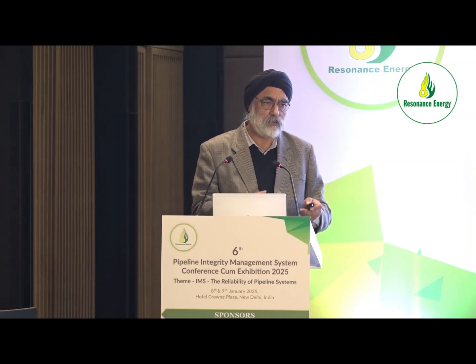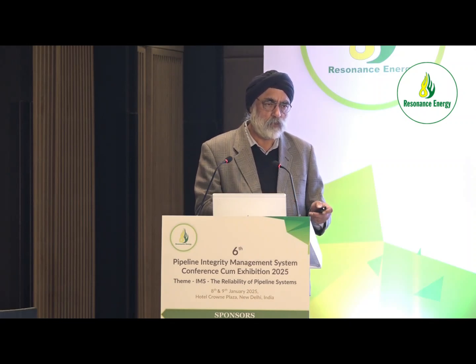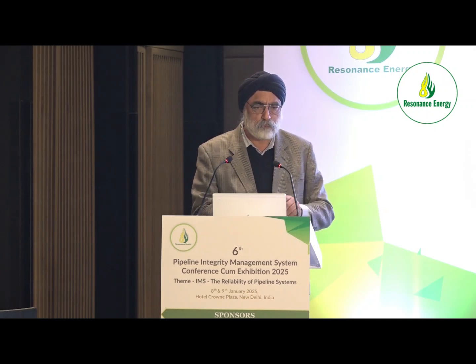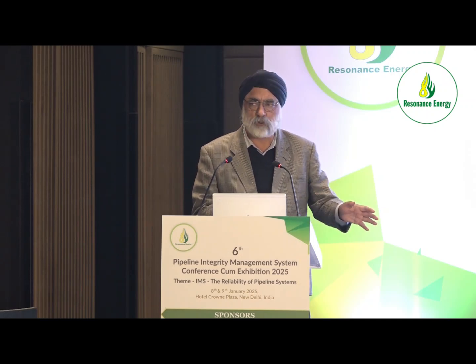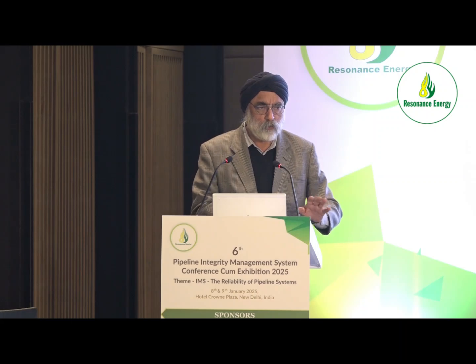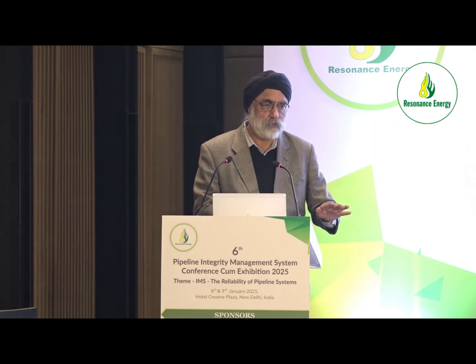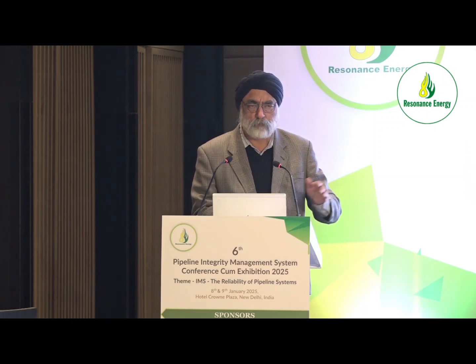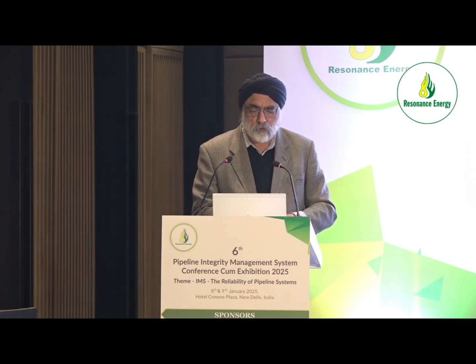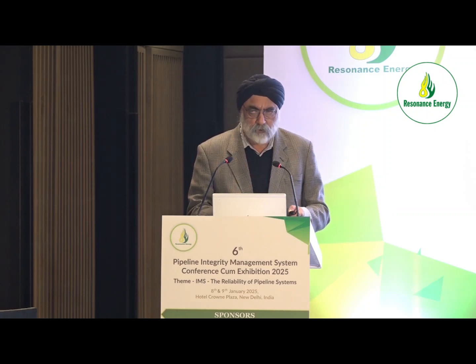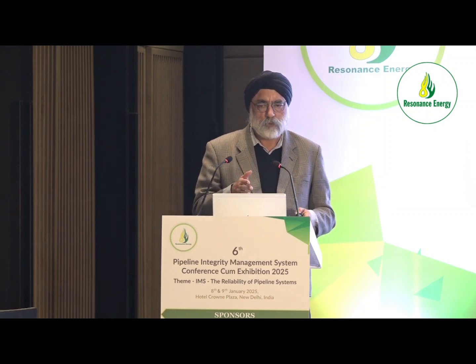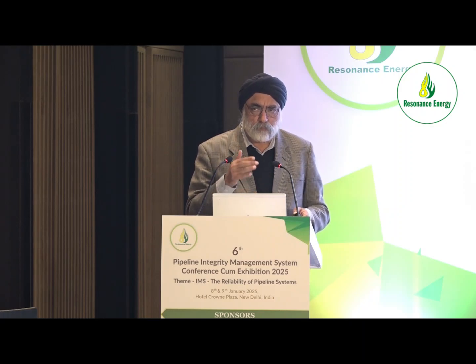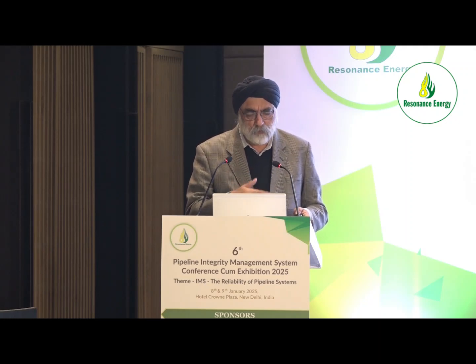We have to earth pipelines at regular intervals. The design says put zinc grounding electrodes, fine, we'll put the zinc grounding electrode in soil. Then nobody does any maintenance, no watering, nothing. The resistance starts to go up and the pipe is again compromised due to AC interference. So a lot of work has to be done. The O&M engineers have to physically go to the sites and learn the whole thing, and the subcontractor people have to learn, otherwise there will be compromises in the city gas distribution networks.